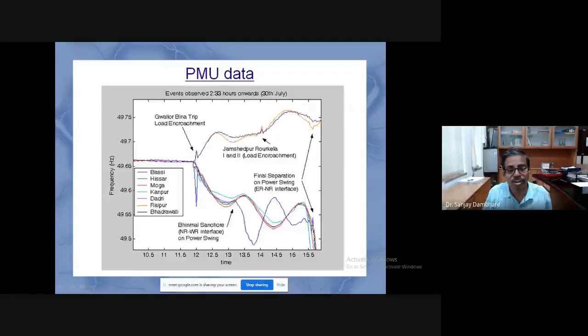So what happened was the Jamshedpur to Raurkela lines were again subjected to load encroachment, and those lines were also tripped. The Bhinmal to Sanchore lines were subjected to power swing, and this distance relay tripped on the power swing, which we discussed earlier, and then the system started further oscillating.